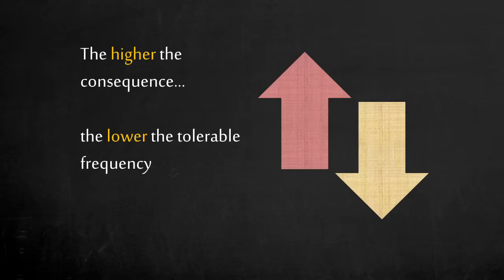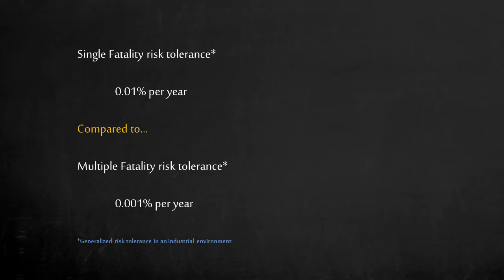The rationale is simple. The higher the consequence, the lower the tolerable frequency. Generally, industry accepts a 0.01% chance of a single fatality in a given year. In other words, the chance of fatality is 1 in 10,000 for an individual per year.